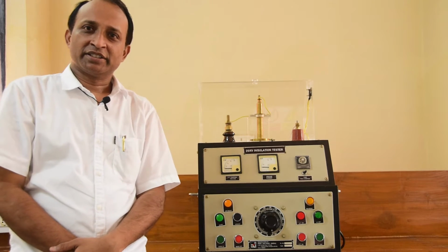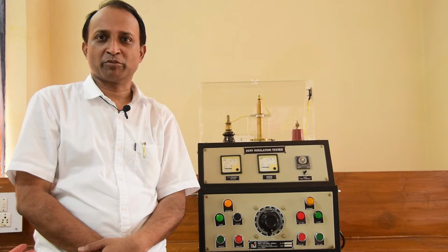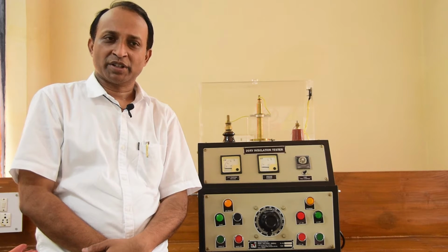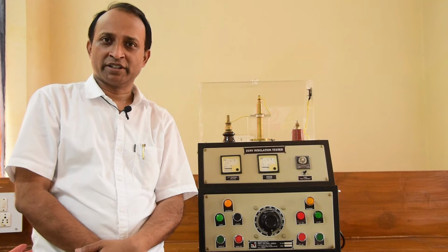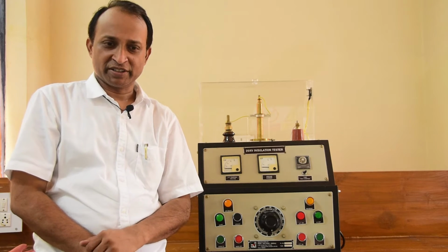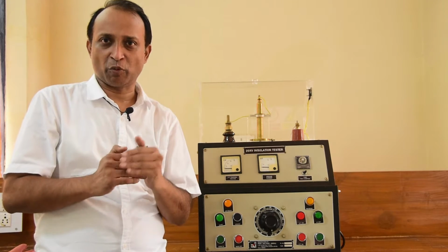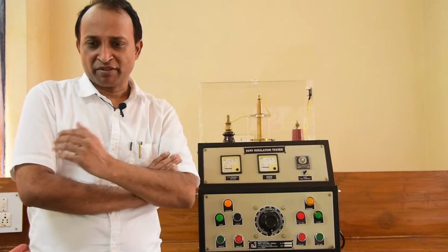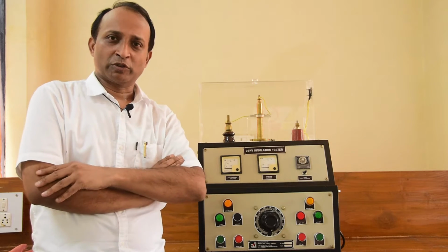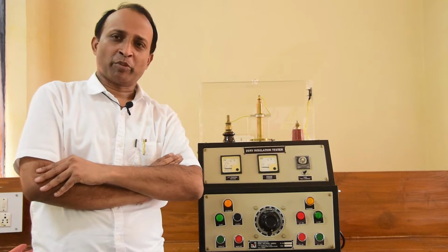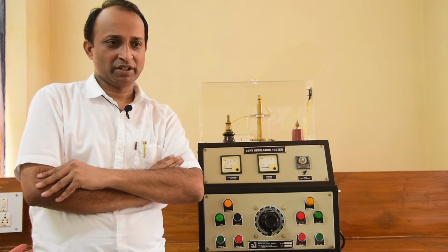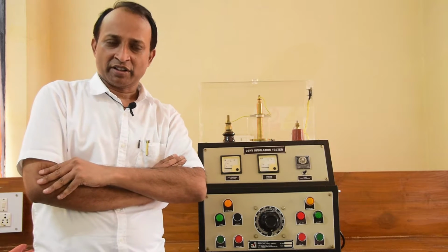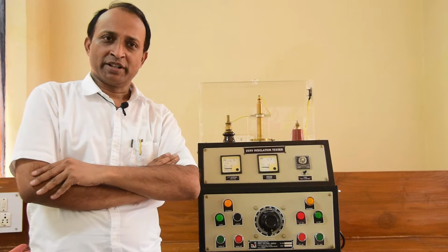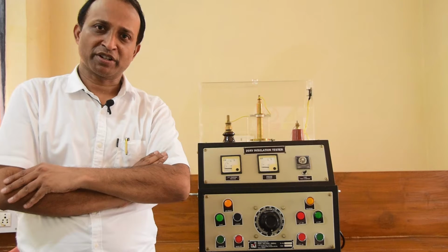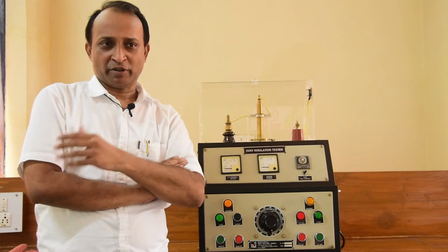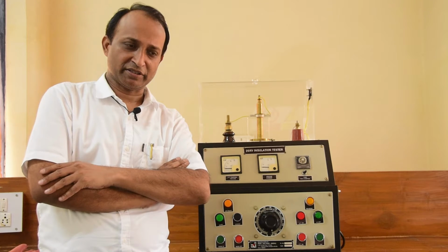So naturally, the most important property of the insulation that must be tested is to determine the breakdown strength of such solid insulator before they are used in the transformer for insulating the coils in terms of inter-turn protection. Similarly, insulating high voltage winding from the low voltage windings. Apart from oil, papers are also used. So also the paper and cardboard insulators, these are used in cables and capacitors in electrical power systems. They provide a dielectric medium in capacitors. Similarly, they provide insulation between the turns or conductors within oil filled cables.